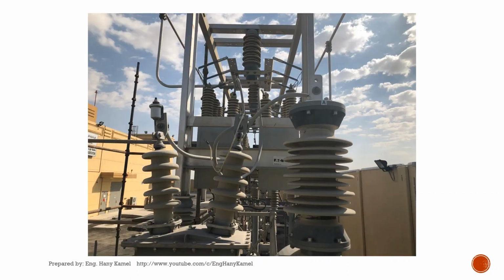Here in this photo, we can see the 2 neutral cables. One is connected to the frame of the capacitor units and going to connect to B1 of the neutral CT. And the other neutral cable is connected to B2 of the neutral CT, and one cable coming from B2 in the neutral CT is connected to B1 of the neutral VT, and only one is connected to the frame of the capacitor units.